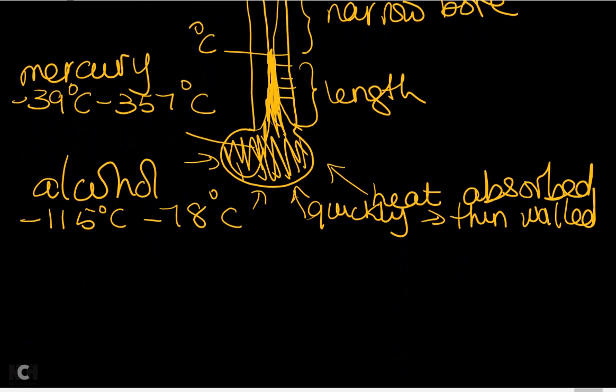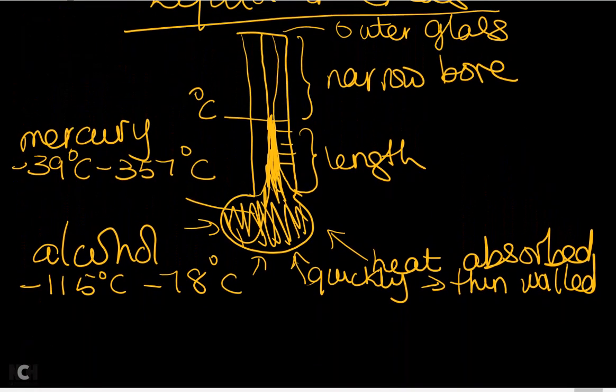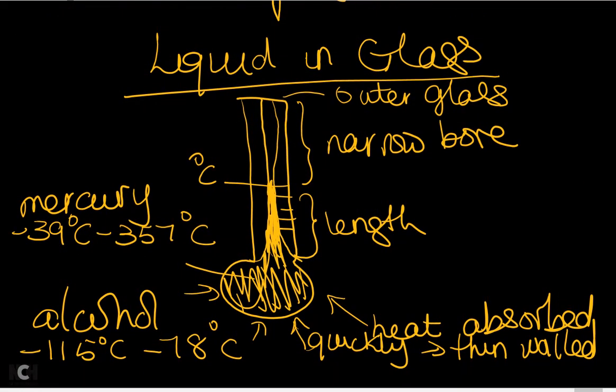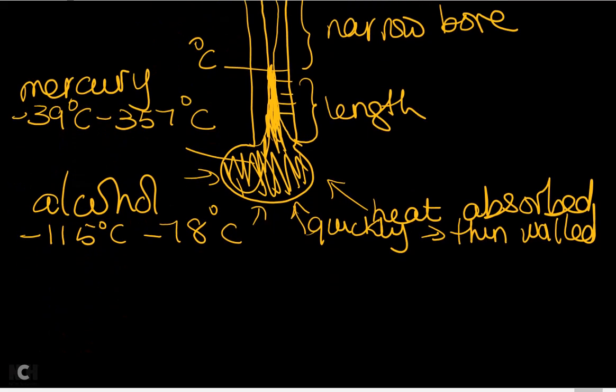Liquid-in-glass thermometers are advantageous because they give a very quick, direct reading. However, for changes smaller than about one degree, it's advisable to use a platinum resistance thermometer or a thermocouple, as liquid-in-glass thermometers are not very sensitive to small changes in temperature.